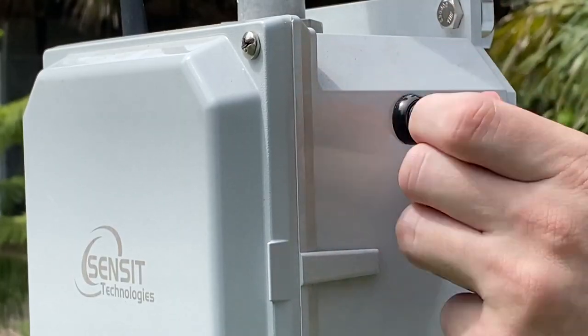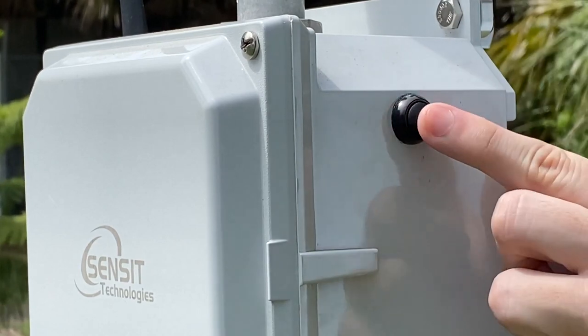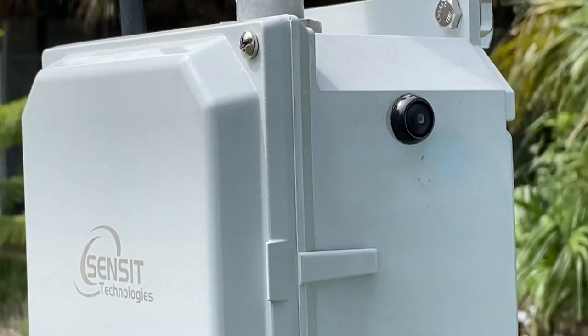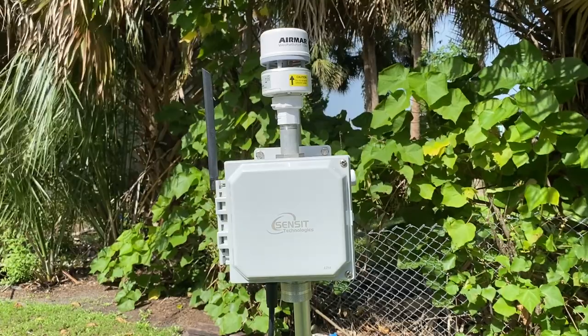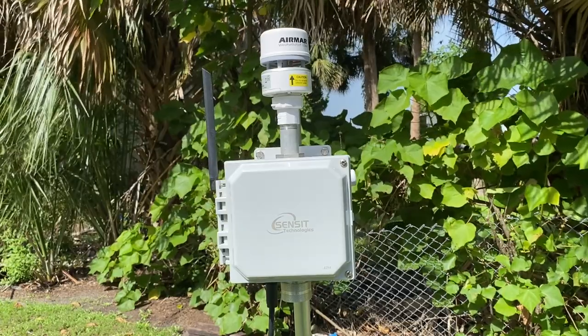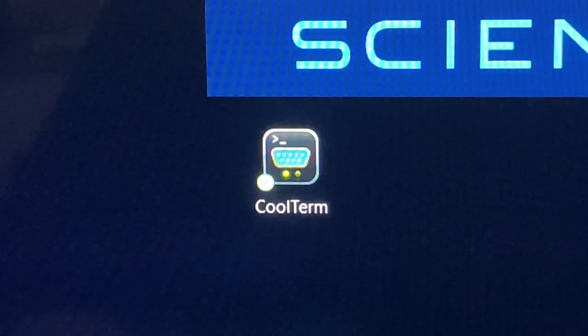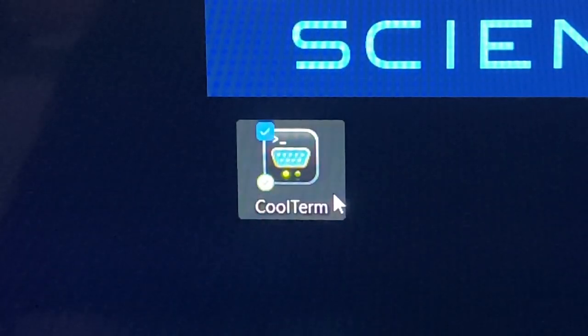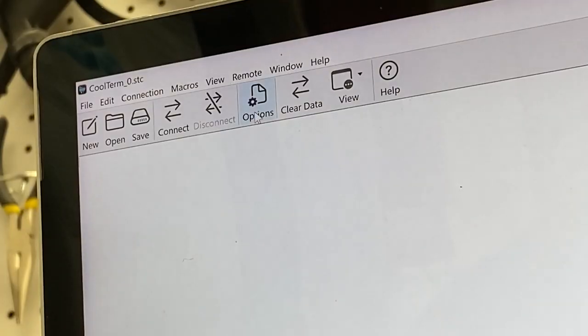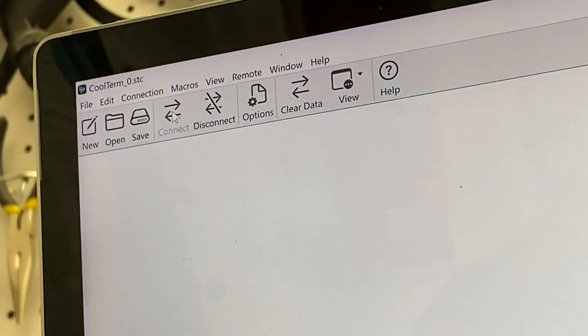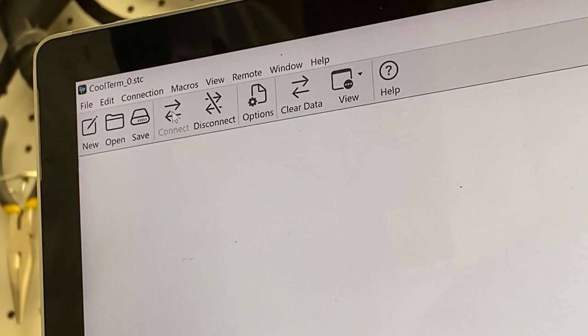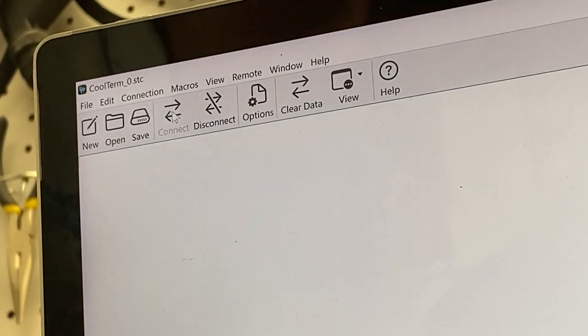Power on the S-Pod unit. The unit must be allowed to run for three minutes before any calibration commands will be acknowledged. Open the CoolTerm application and click on the Connect icon. This will allow the S-Pod and computer application to communicate.